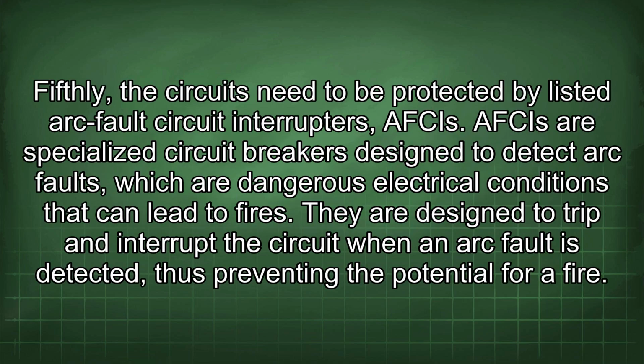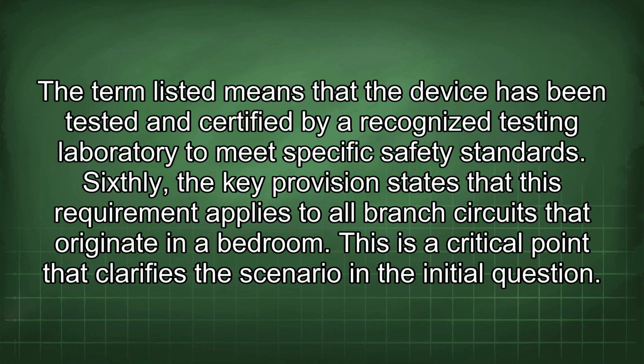Fifthly, the circuits need to be protected by listed arc fault circuit interrupters, AFCIs. AFCIs are specialized circuit breakers designed to detect arc faults, which are dangerous electrical conditions that can lead to fires. They are designed to trip and interrupt the circuit when an arc fault is detected, thus preventing the potential for a fire. The term listed means that the device has been tested and certified by a recognized testing laboratory to meet specific safety standards.